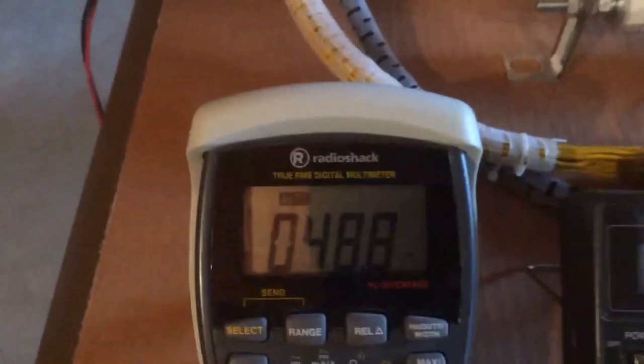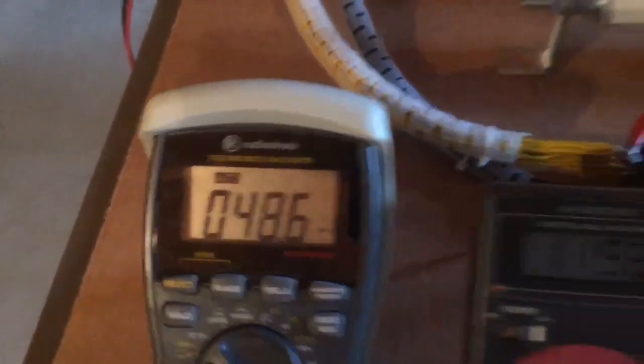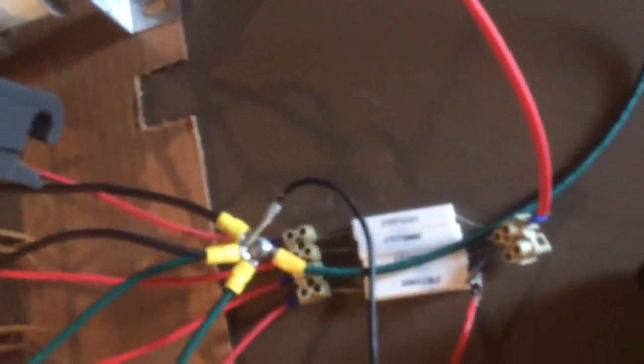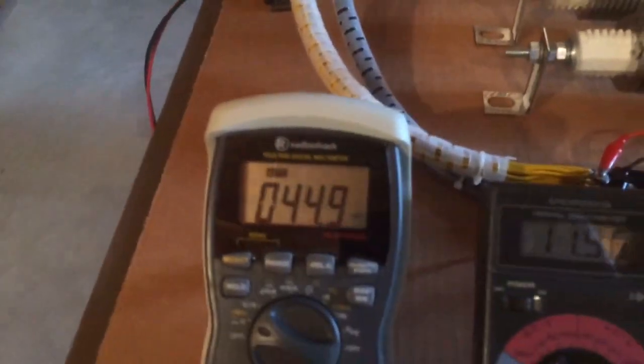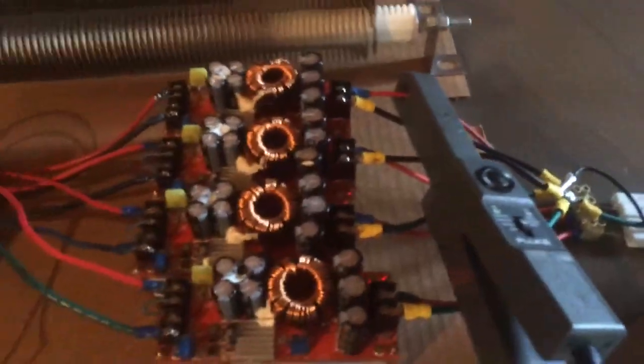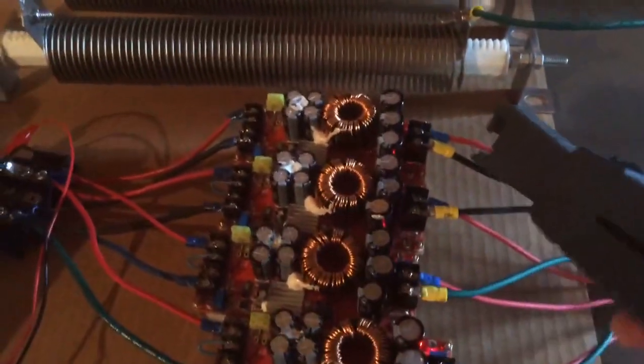And the third one four point eight amps, remember you have to carry the zeros, and finally we snap it on the last one, and about four point five amps. So you can see again that the load is evenly distributed.